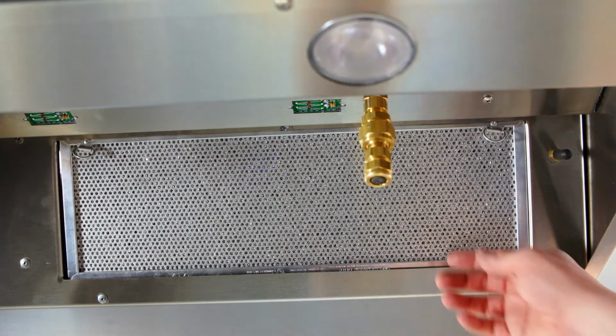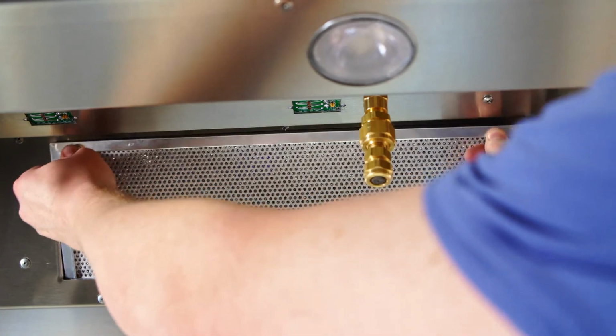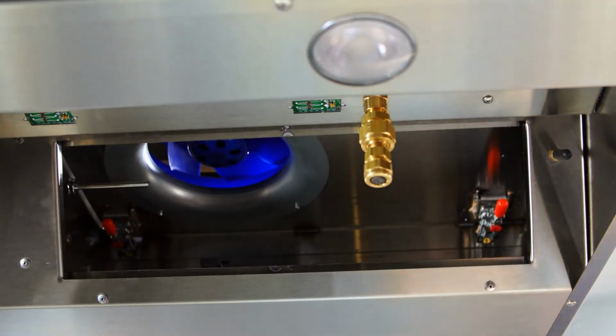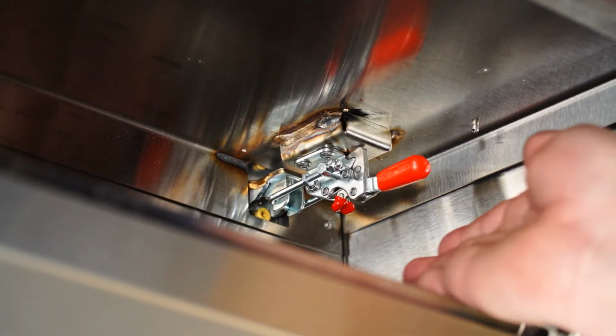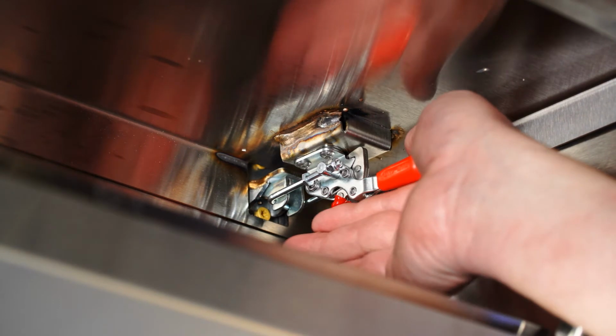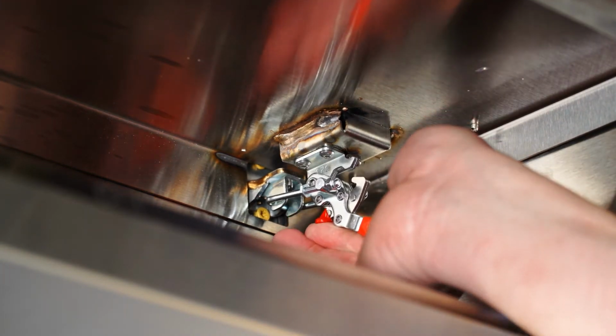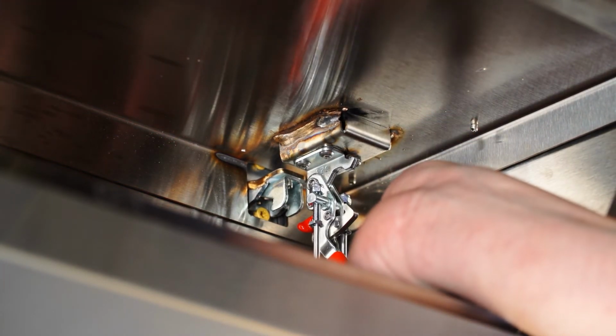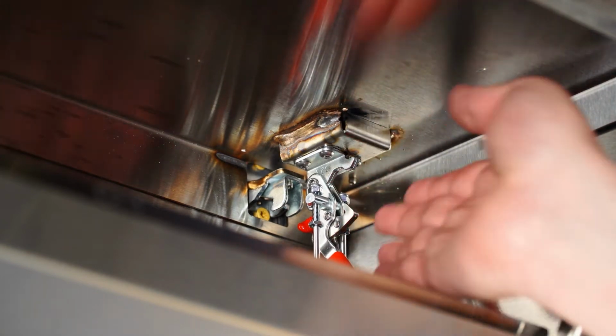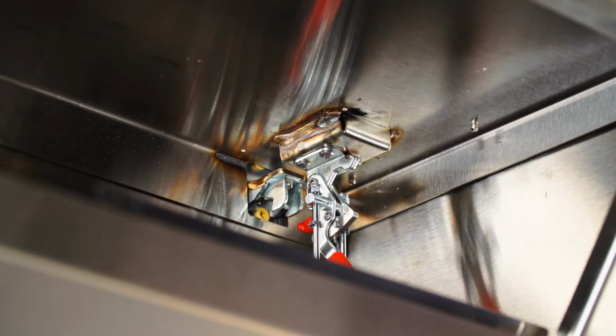Let's begin by lowering the hood into the service position. Pull down on the two tabs and release the mesh filter from its rack. Once you remove the filter, you will see two clamps in each corner holding the hood upright and in its normal position. With a helper to support the weight of the hood, press the red button on the bottom side of one clamp to unlock it. Then pull the large red handle down. Repeat this on the other side.